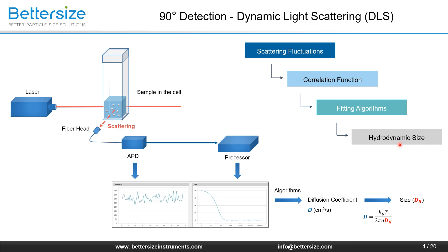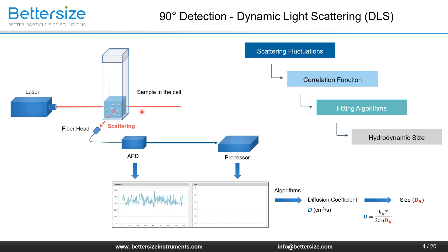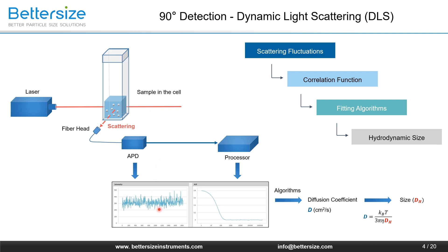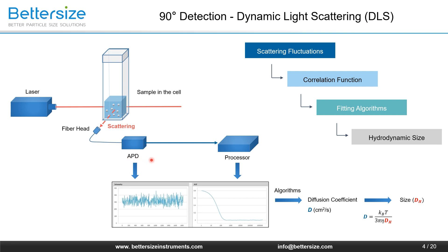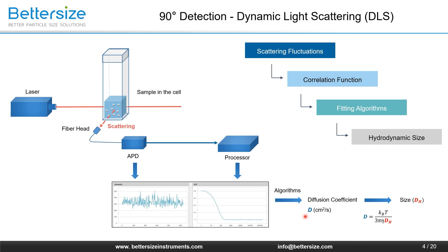In a conventional DLS analyzer, a coherent laser beam illuminates the uniformly dispersed nanoparticles in the sample cell, which scatter light in all directions. The scattering intensity fluctuates over time due to the continuous random Brownian motions of particles. The APD detector determines the number of photons in scattered light at 90 degrees, and the processor computes the sample's autocorrelation function. The diffusion coefficient is then calculated and used to give the hydrodynamic size through the Stokes-Einstein equation.